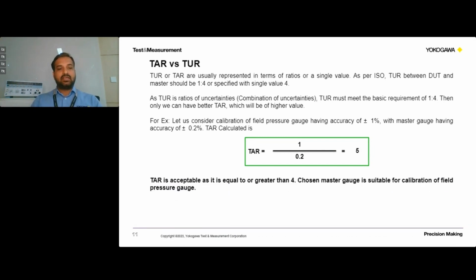That means the master gauge which we have chosen to calibrate the pressure gauge which is having 1% error, and we are calibrating that gauge with the master gauge which is having 0.2%. That means the master gauge which we have chosen is meeting our requirement. So the master gauge which we have chosen is a right standard or right master instrument for calibration of the particular pressure gauge.